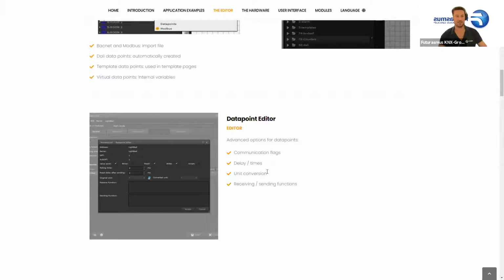This data point editor is nice to have if you want additional features, like polling, if you need to poll the installation because the heating system doesn't send temperature with the right frequency. You can set the polling time and set unit conversions, because maybe your energy meter sends watt hours, but the customer wants to see kilowatt hours. You just set the unit conversion, say you receive watt hours but want kilowatt hours, and then throughout the whole system you will have kilowatt hours in the process point. There are many features like that you can set up in the data point.